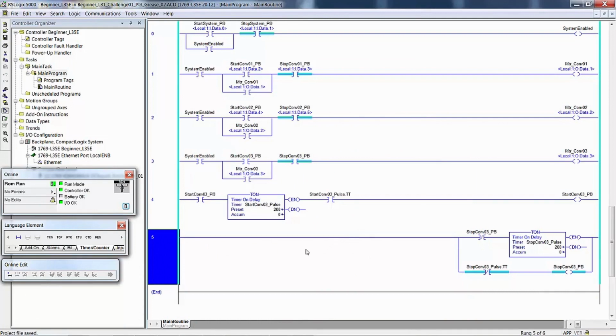You wouldn't do this out in the field when you save your project files. Whenever you go out to a machine on the plant floor or at the customer site, you always immediately upload what's in the machine and save it with a name that you recognize with today's date.